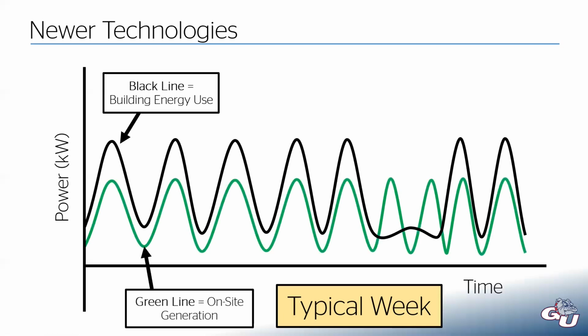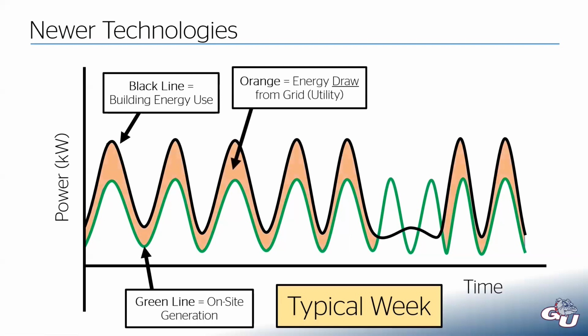And let's say we have some on-site renewable energy generation, this green line. Let's say that's solar PV panels, meaning we get more generation at the peak of the day when the sun's nice and high, which happens to be at the same time that our air conditioning systems are peaked out. And then it drops as we get to nighttime. And so we're always just offsetting some of our energy, but not all of it. So this area in orange, that would be the amount of energy draw we would need to pull from the utility. So we would still need to be getting electricity from our utility provider. Not as much as a regular building, but we still need some. So we can't disconnect from the grid entirely.